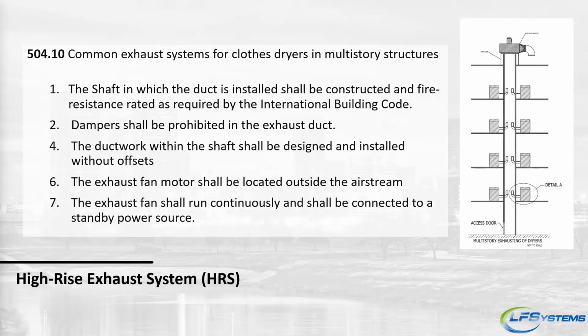We've also used that. There are other uses for it. Obviously, we're focused on the high-rise exhaust, but with our stairwell pressurization, that typically is going to be in a fire-rated shaft. We've used it flipped, where it's no longer an exhaust pipe; it's an intake shaft. That one obviously doesn't have the subducts, but it does still have the tap, so we can have the fire rated duct prefabricated, so you're not having to wrap that or deal with that. So great question.